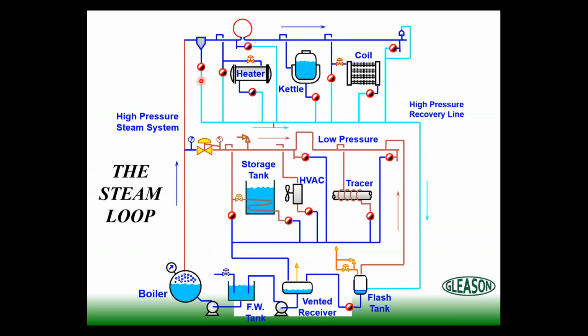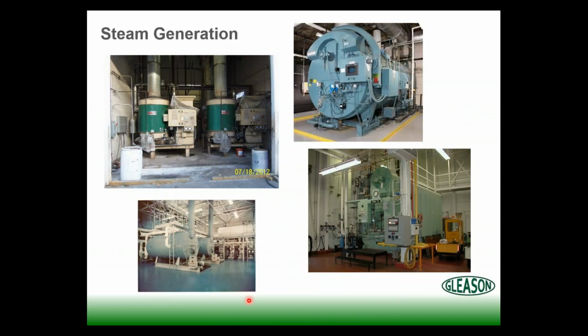And then all these symbols here, what are those symbols? Many of you know, some may not, but all these little red and black and white symbols, those are steam traps. And steam traps are what I call the gatekeeper between the steam portion of the system and the condensate portion of the system. We'll talk a little bit more about them in a minute. And then, hopefully to close the loop, we want to bring that condensate back to the boiler room, boiler plant, and use that again. So very cost effective to do so in most cases.